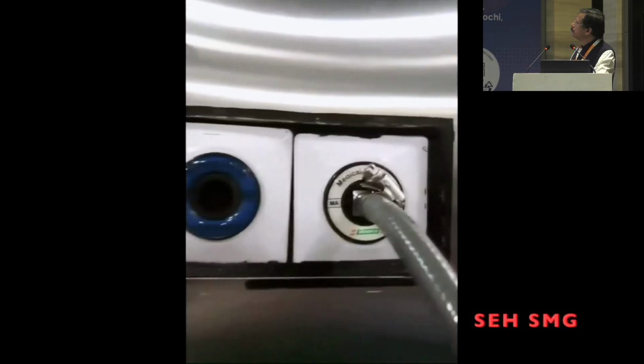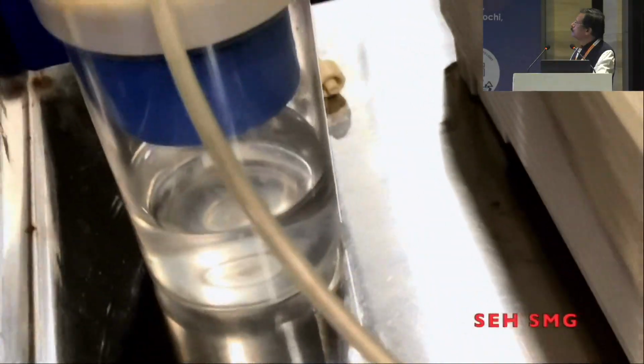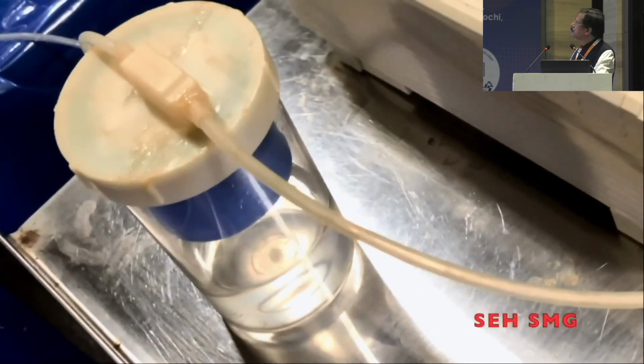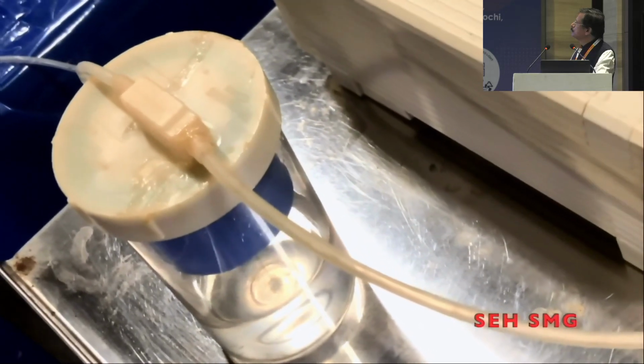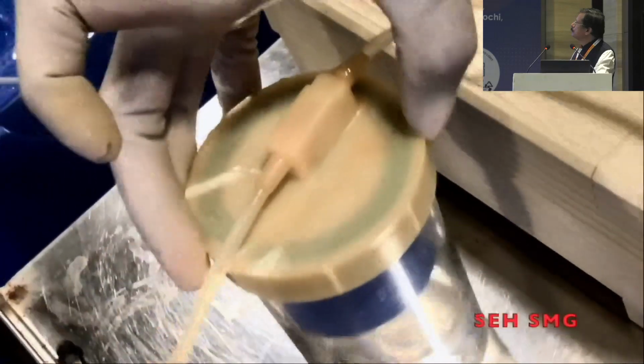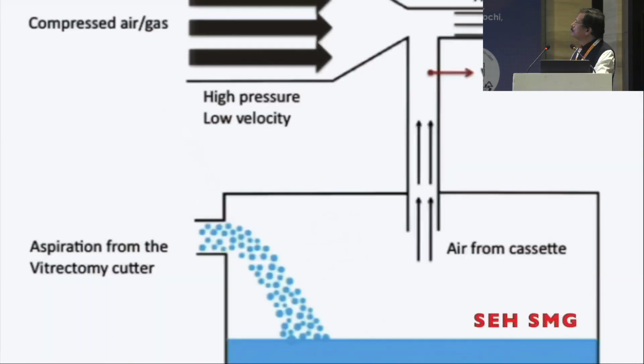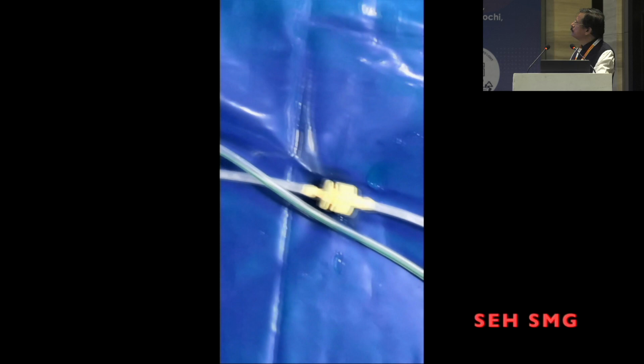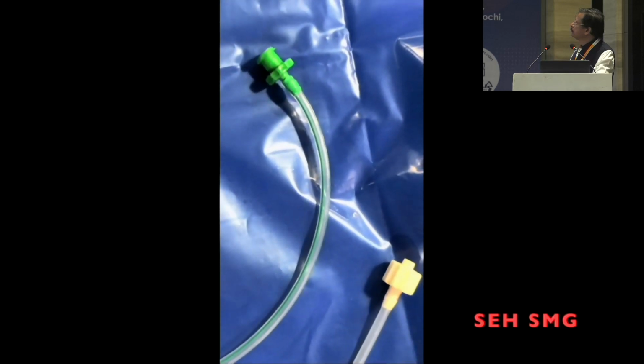And the air comes from the central compressed air outlet in our hospital, and also these machines will come with small tiny compressors. This is a small bottle which helps to create vacuum by the Venturi pump system. This is the cutter with two tubes. One is in blue color, the other one is in white color. The blue is for the cutter and the white one is for vacuum. So one should not confuse them when you are setting it up.